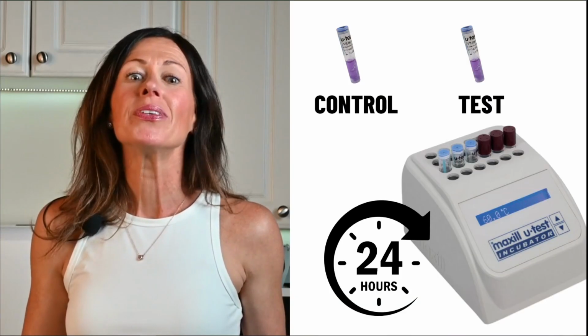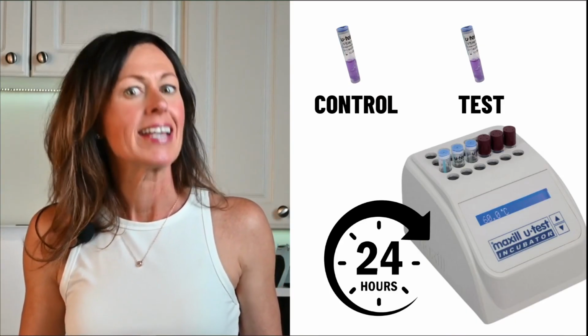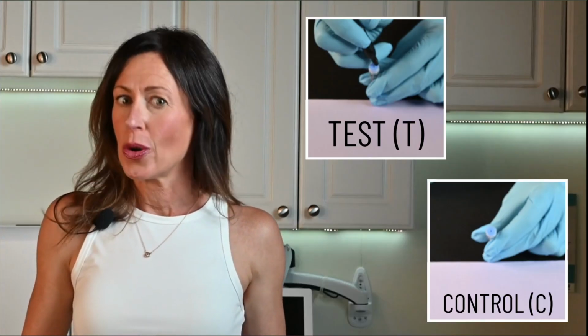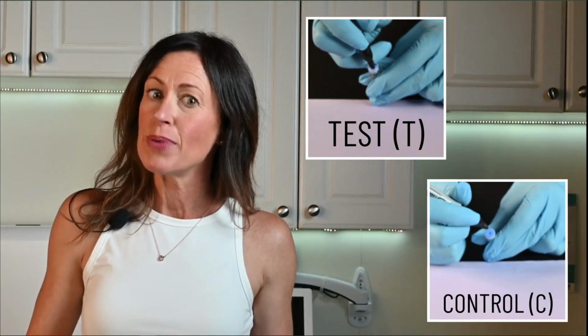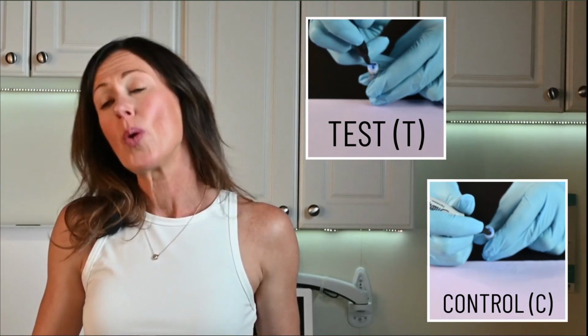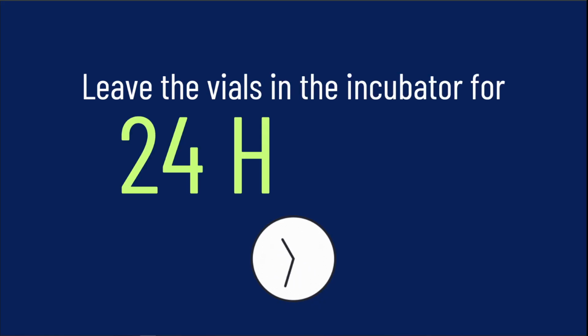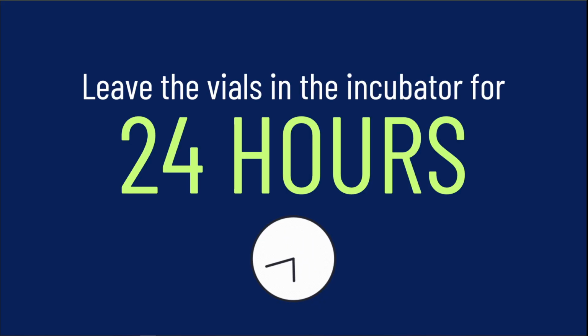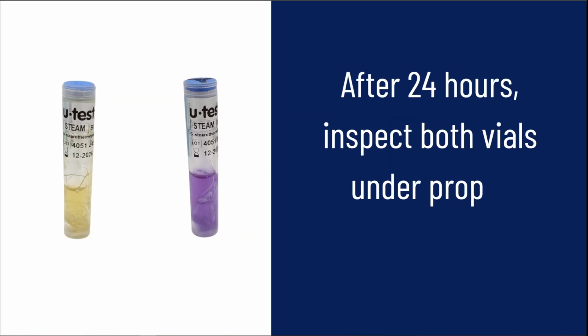Next, place both the test vial and the control vial into the incubator. Be sure to note their position and label the test BI with a T and the control BI with a C. Leave the vials in the incubator for 24 hours. During this time, any surviving spores in the vials will begin to grow and cause a color change in the media. After 24 hours, inspect both vials under proper lighting.